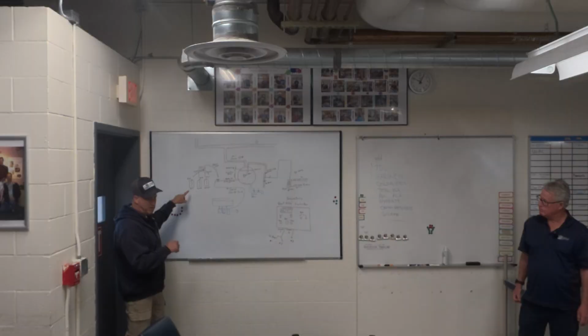You have to measure that a bit because there's less oxygen in hot water, correct? But as you add new cold water when bringing the boiler online, there's a lot of unbonded oxygen, and we want to bond it up as quickly as possible. Our boiler compound actually has sulfite in it too, so if it's cold and you're going to refill the boiler, make sure you put 5 gallons in the new ones and 10 gallons in the bigger ones to kickstart it.